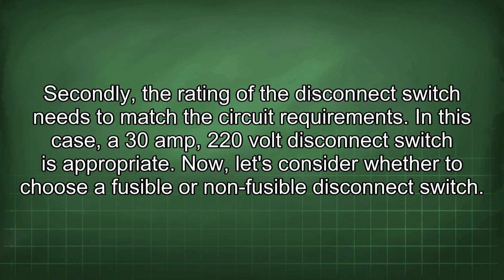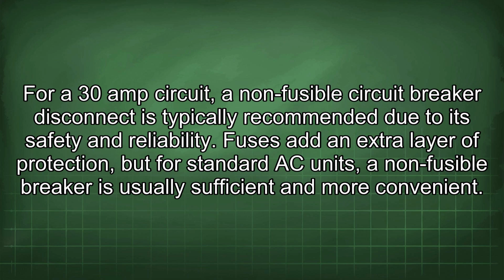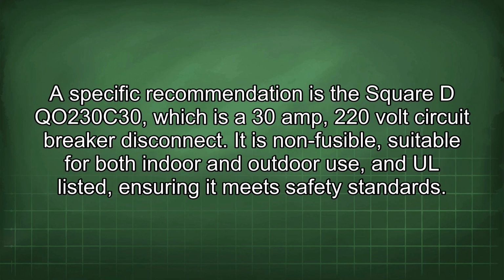Now, let's consider whether to choose a fusible or non-fusible disconnect switch. For a 30 amp circuit, a non-fusible circuit breaker disconnect is typically recommended due to its safety and reliability. Fuses add an extra layer of protection, but for standard AC units, a non-fusible breaker is usually sufficient and more convenient. A specific recommendation is the Square D QO230C30, which is a 30 amp 220 volt circuit breaker disconnect. It is non-fusible, suitable for both indoor and outdoor use, and UL listed, ensuring it meets safety standards.